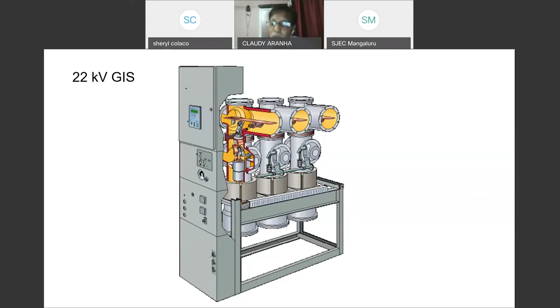Similarly, we have got GIS for distribution, for 22 kV and 11 kV circuit breakers. Also, we have got gas insulated switchgear. You can see the bus bars are enclosed in the SF6 pipes, and the circuit breaker is vacuum switchgear. Everything is either vacuum or GIS, very compact. Now, this provides reliability. Faults are very less, everything is reliable, maintenance free.